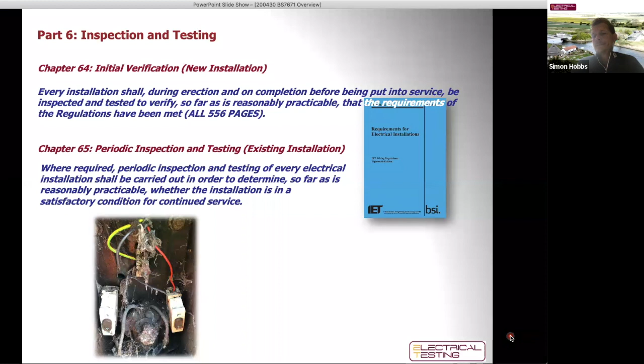Chapter 65 deals with periodic inspection and testing. This is where we go into an existing installation, and again they're looking to check that it conforms with the regulations, but it's a little softer. Where required, periodic inspection of every installation should be carried out in order to determine, so far as is reasonably practicable, whether the installation is in satisfactory condition for continued service. They're looking to make sure it's still safe. It doesn't have to be perfect, but it does need to be safe.